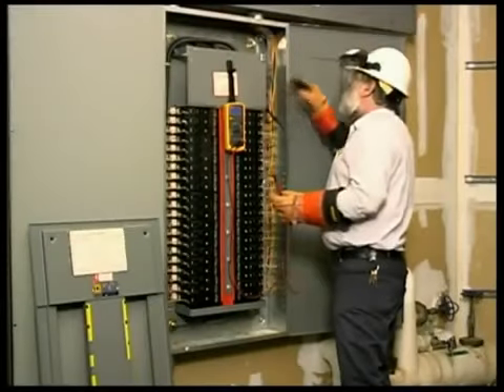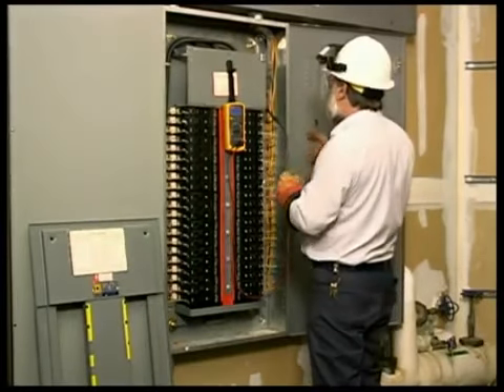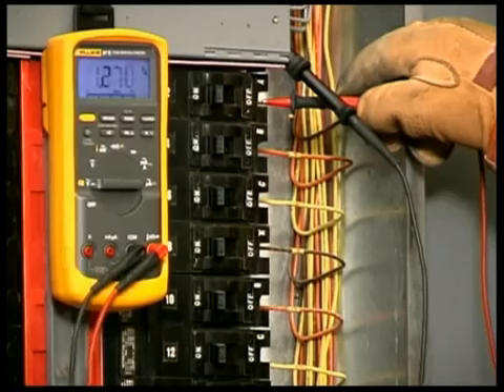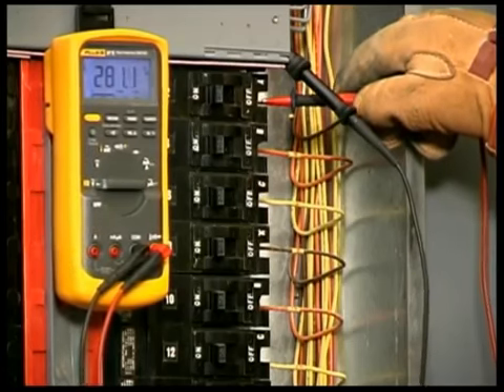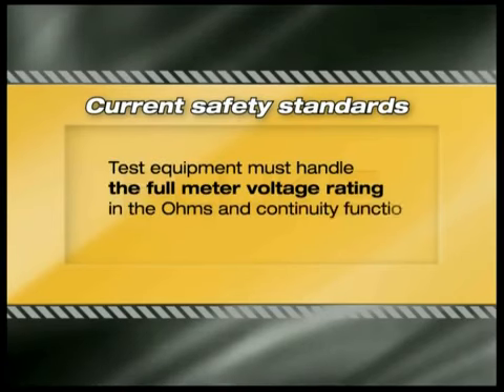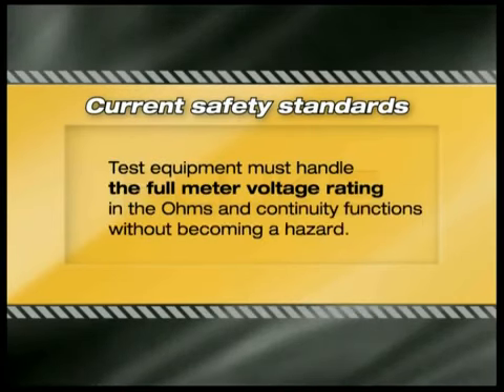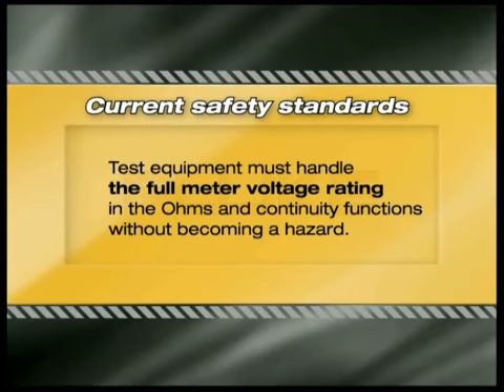Even the most careful of us will make mistakes. That's why your meter should offer a margin of protection. This principle is so important that it has been written into current safety standards. The standards require that test equipment must handle the full meter voltage rating in the ohms and continuity functions without becoming a hazard.